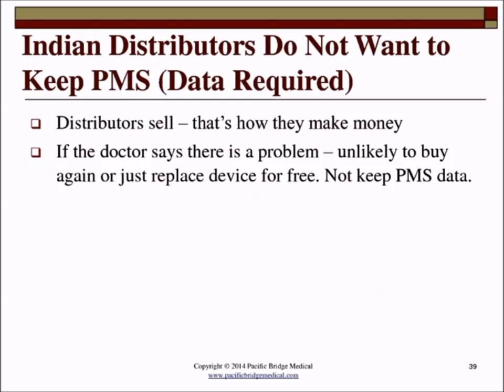And as I mentioned, why will your Indian distributor keep post-market surveillance data if the doctor won't buy again, or if the doctor is happy with the replacement device that you provide because of the defect in the device you already sold? And I'd say that in general, almost all Indian distributors are not aware of Indian and global regulatory requirements for complaint handling and the quality of the information that's required to be collected. Again, from our experience, almost all Indian distributors are not aware of these requirements for complaint handling and collection of information. So when you're doing the re-registration, it could be very difficult to get the PMS data from your Indian distributor because they're not keeping a copy of that.